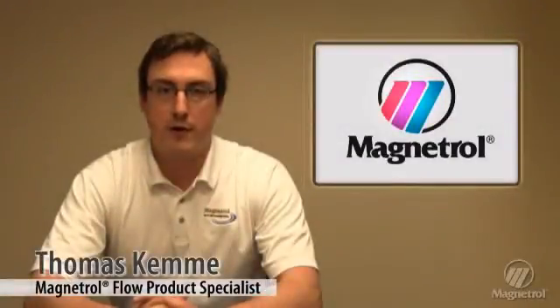Today we are going to show how to verify that a Thermatel model TA2 is still within calibration. When a TA2 leaves Magnetrol, it is already pre-configured and calibrated for the specific customer application. We consider the calibration a permanent one.